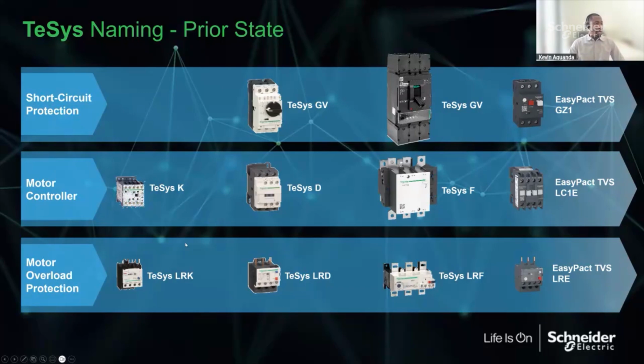So in the past, our core offer essentially had these four ranges. So from TeSys K, which is more of the miniature contactors, applications where we're looking for a compact solution with limited space for these types of requirements. Then we had our standard offer of TeSys D, so the LC1D range, covering applications from 9 amps to 95 amps AC3. We had the TeSys F for more high power requirements. Each of these, of course, coming with a set of overload relays and the motor protection breakers for the respective rating of the contactors that we would have. And then again, for standard applications with more cost optimization, we had the EasyPact TVS series in the last few years.